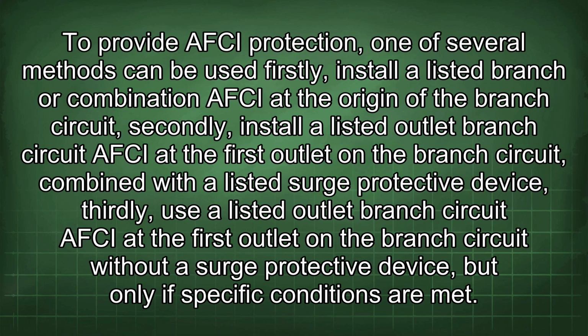To provide AFCI protection, one of several methods can be used. Firstly, install a listed branch or combination AFCI at the origin of the branch circuit. Secondly, install a listed outlet branch circuit AFCI at the first outlet on the branch circuit, combined with a listed surge protective device. Thirdly, use a listed outlet branch circuit AFCI at the first outlet on the branch circuit without a surge protective device, but only if specific conditions are met.